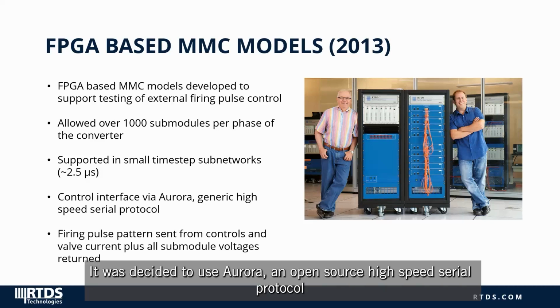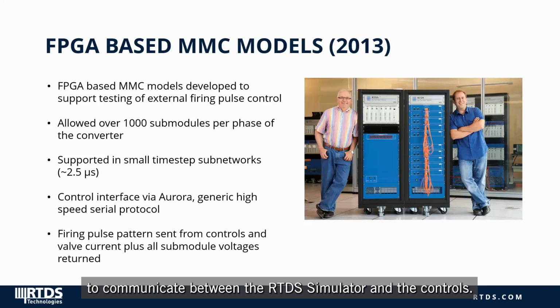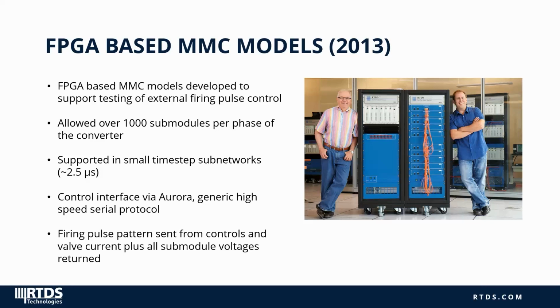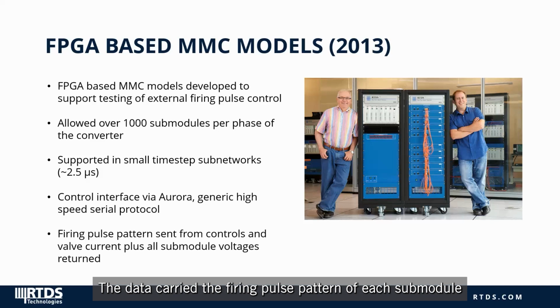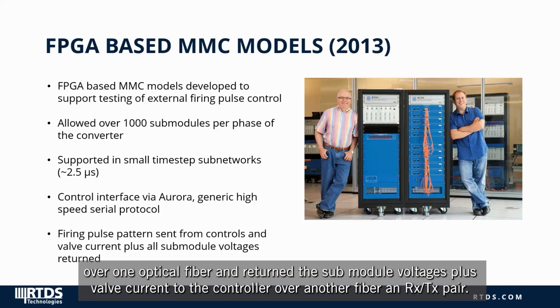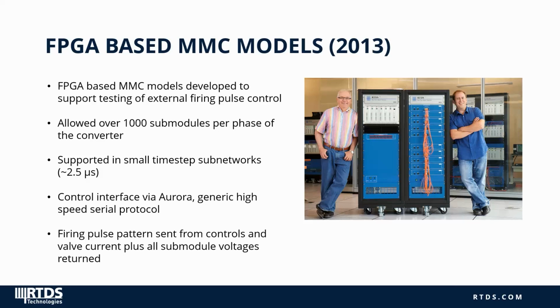It was decided to use Aurora, an open-source, high-speed serial protocol, to communicate between the RTDS and the controls. The data carried the firing pulse pattern of each submodule over one optical fiber and returned the submodule voltages plus valve current to the controller over another fiber, an RX-TX pair.